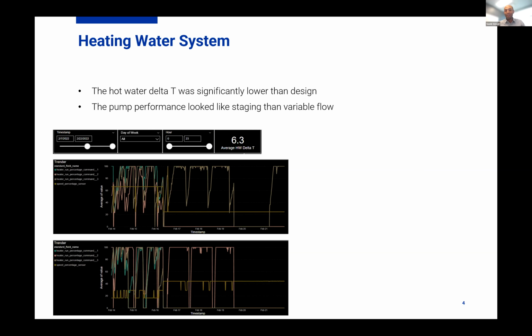What we figured out was that the internal sequence for our boiler controllers wasn't set up as designed. Instead of getting a variable flow system that can reduce pump flows as much as possible and give us the greatest delta T, we had a boiler system operating based on stages, so the pumps were running at 30, 60, 100%, and that's it.